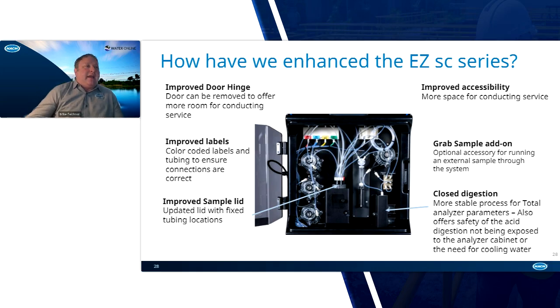variability. We did also include a grab sample feature, which I'll show on the next slide. And then the other thing is the closed digestion. Before, you saw the picture with the glass vessel and a number of connections, and we had to have cooling water. Now we can do air cooled, and everything can be done in this pressurized heating chamber where we can break down the material from total complex material to dissolved ones.